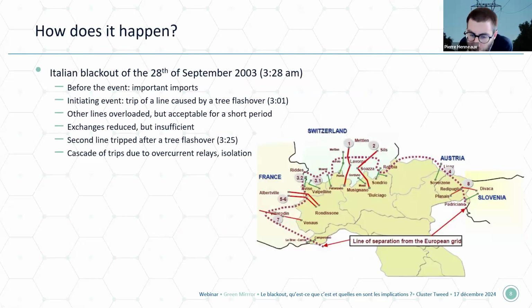To understand how it happened, we need to know what was the state of the system before we had failures in the grid. It was a moment when Italy was importing a lot of electricity, basically from France, but because the electrical grid is meshed, a part of the power was going also through Switzerland. And so the initiating event, the first failure that happened in the grid, was the trip of a line caused by a tree flashover. You see here on the map a line in red with a number 1. Number 1, it was the first failure.